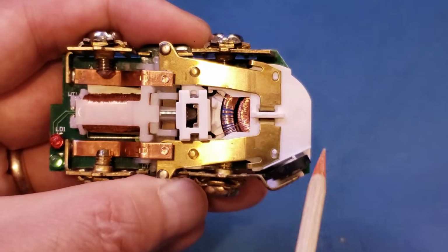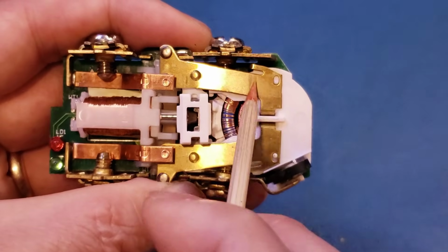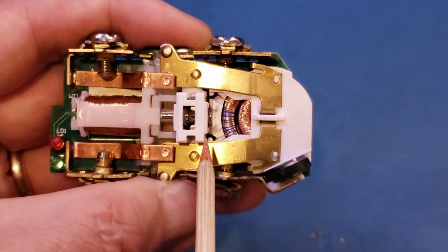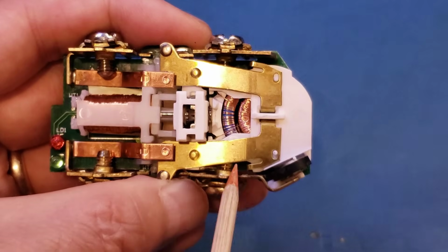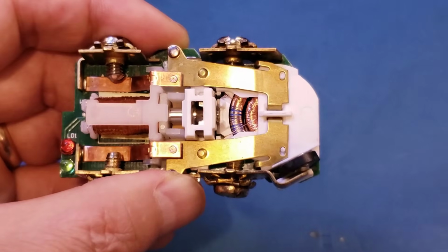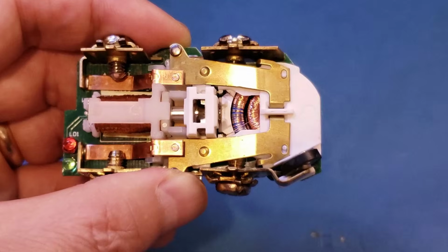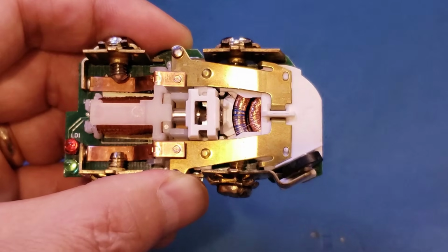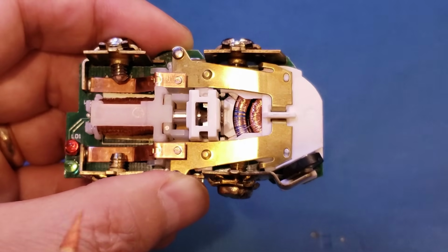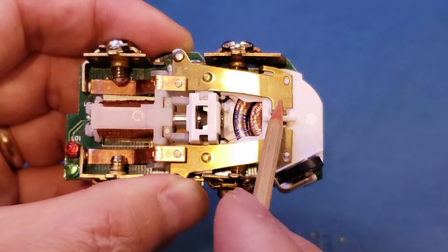Now, if you look carefully, you will see that we actually have two of these concentric cores here, and they're actually two separate current transformers. Why do we have two transformers here? Well, for ground leakage detection, we only need one. And I think the leakage current is being picked up by the inner core here.